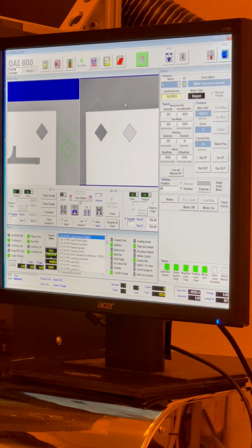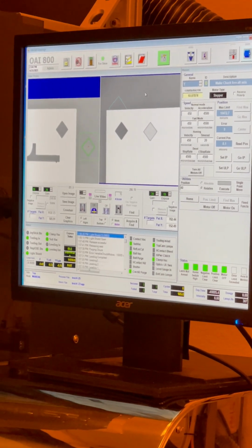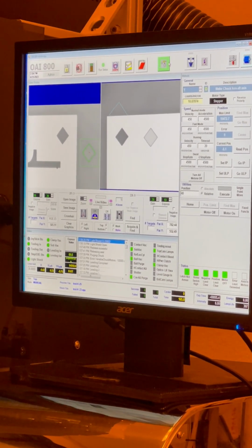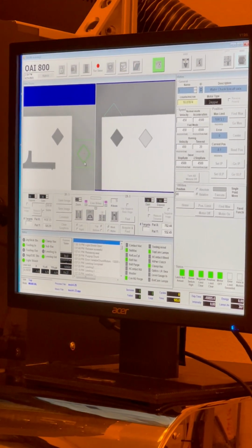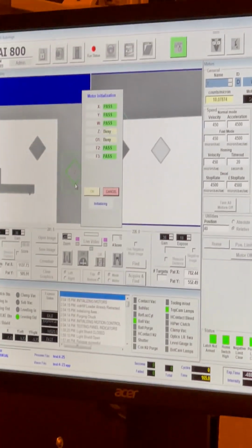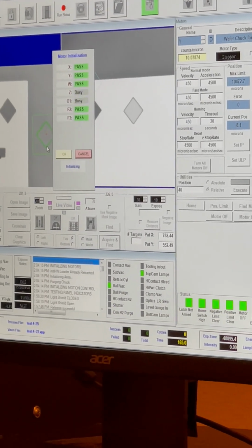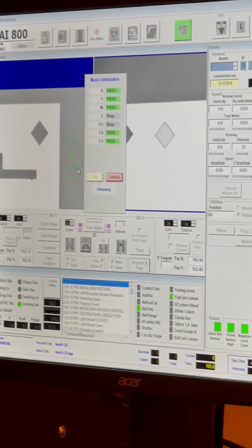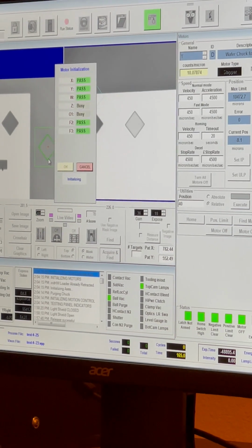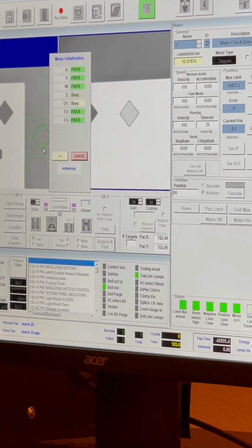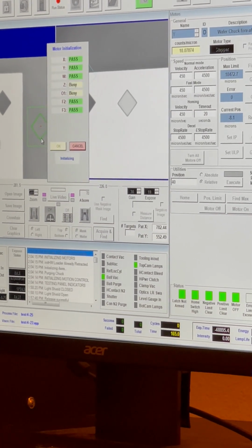To set up the tool, when the tool first comes up, you have to log in, and then you come here and initialize the hardware. Just say yes, and we'll go through this initialization routine. It's usually pretty quick. It's going to take longer now because our z-axis is all the way up. It's going to drive down real slow. Mask, pretty straightforward. Sample holder.